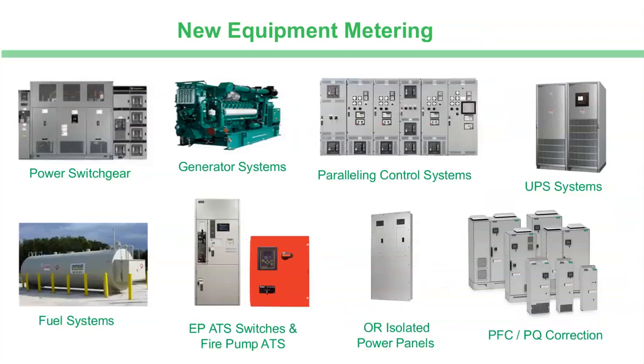When you're looking at new equipment, all of these different types of equipment are places where you should consider metering. Obviously, your power equipment, you want to be able to service and meter your services, both your normal power and your generators. If you have multiple generators, you may very well have paralleling equipment. That is the perfect place to have smart meters that can communicate and tell you everything going on. But then we also need to take into consideration fuel systems and batteries that are serving the generator. Want to make sure that we know the state, if there's any alarms, the amount of fuel. And if we're monitoring generators and fuel systems, it's pretty common that we can also calculate the available runtime with the fuel available, which can be very helpful in a crisis.